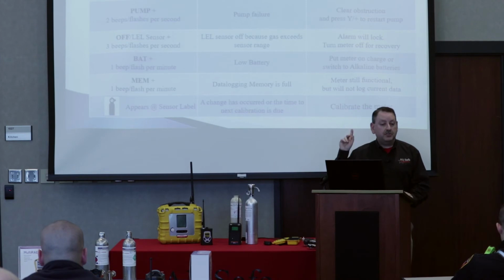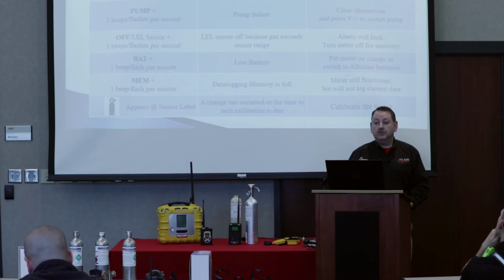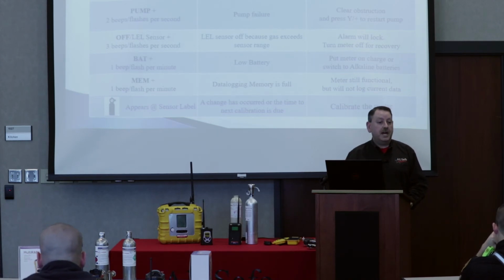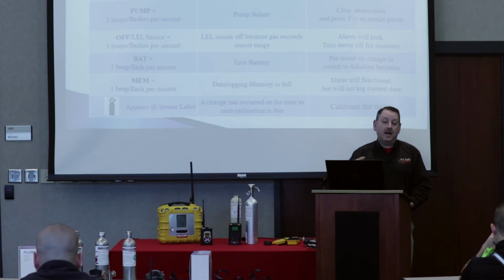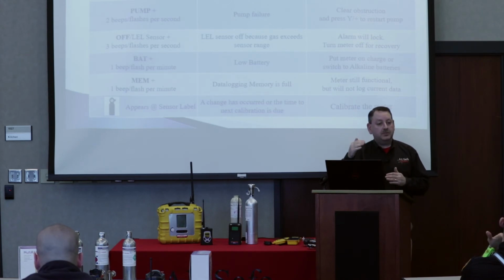So it could be that your sensors are in high alarm, meaning they've exceeded the high alarm limit. You're going to get 3 beeps and 3 flashes per second, and it just means that you've exceeded the high limit alarm on that particular sensor. Bear in mind, your MultiRAE is a 5-sensor instrument, so you could have multiple sensors in high alarm simultaneously. It's also not too far-fetched to think that you could have a high alarm on one of the toxic sensors and a low alarm on your oxygen because the oxygen's been pushed out of the space. So you could have a low alarm and a high alarm going off at the same time.